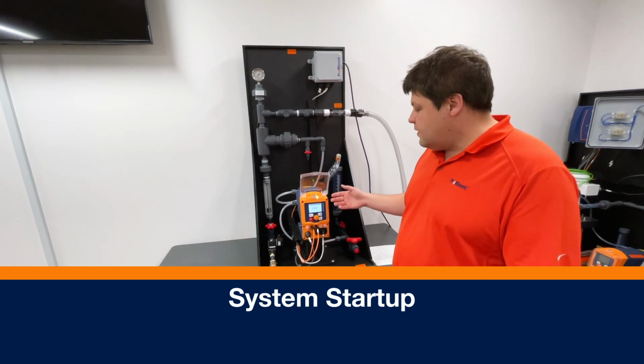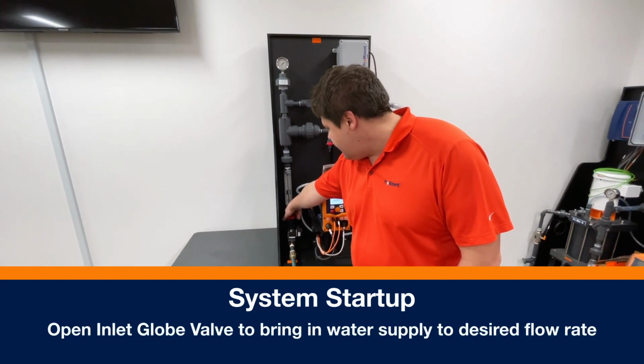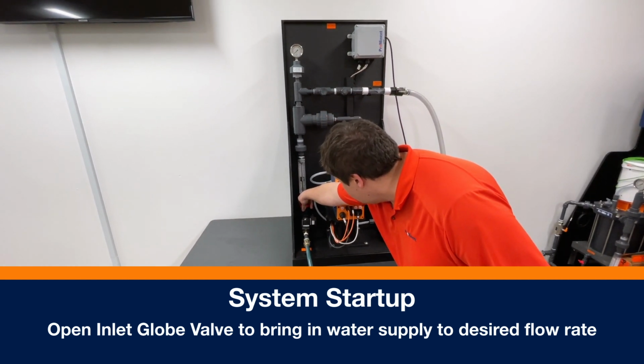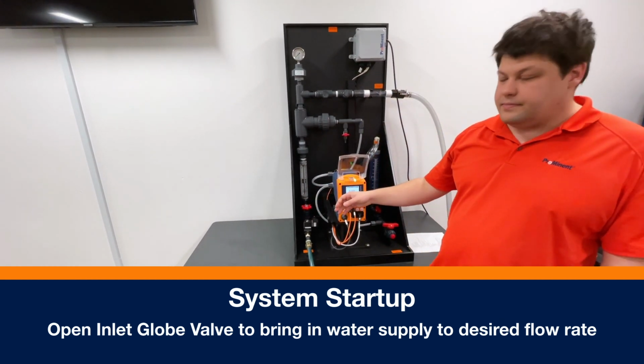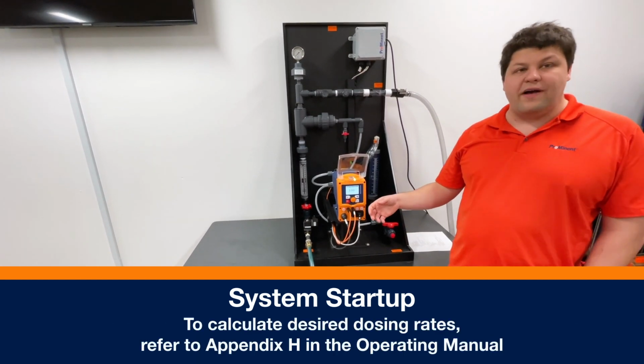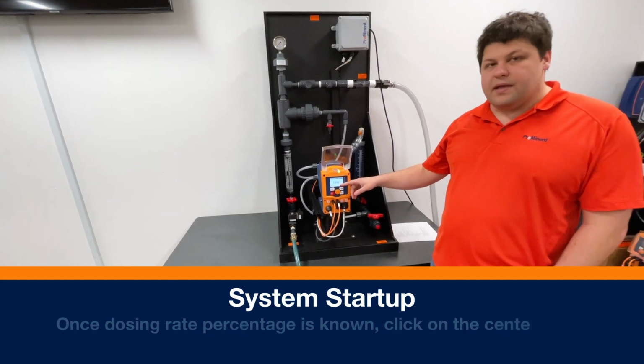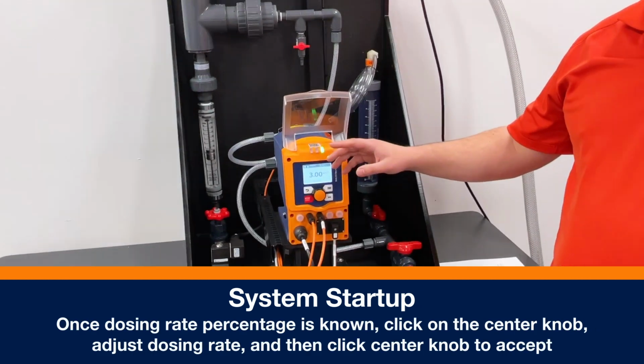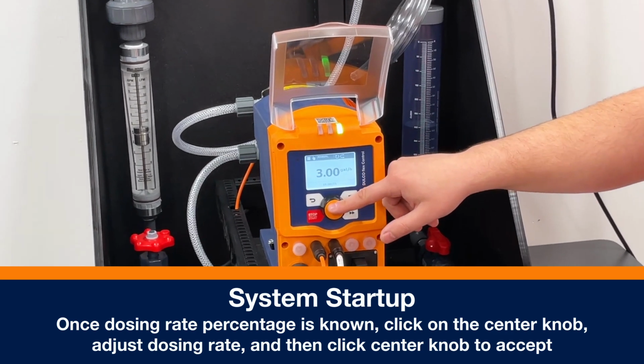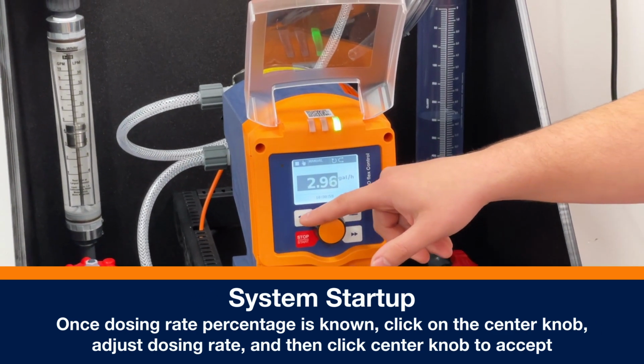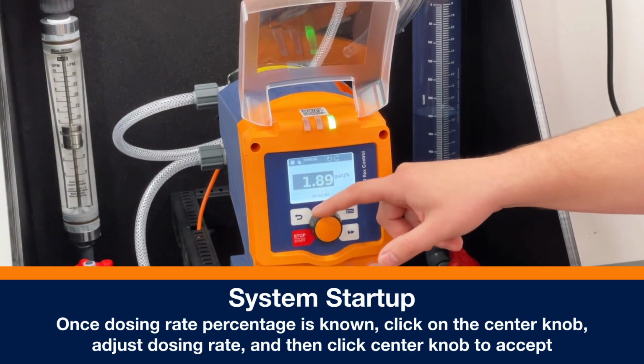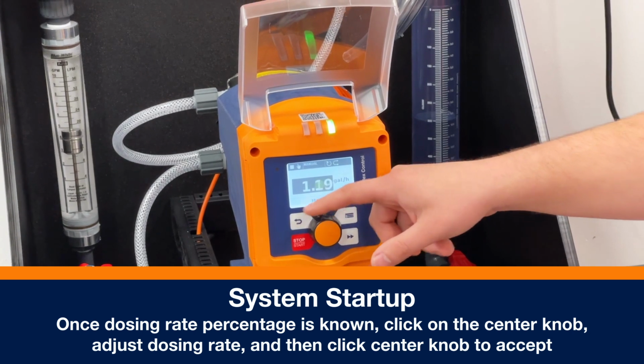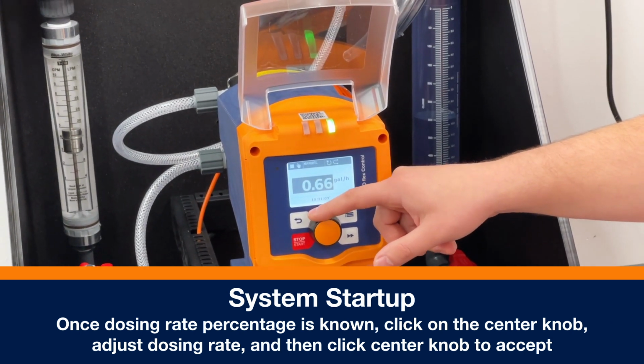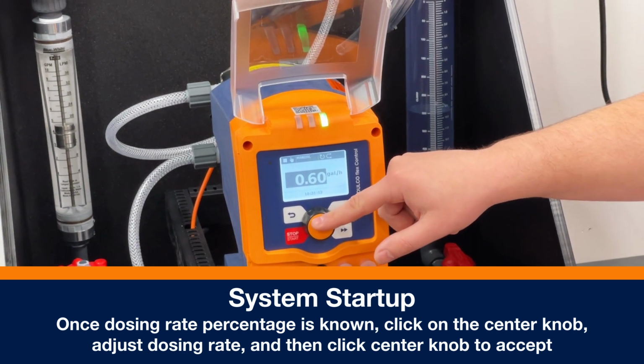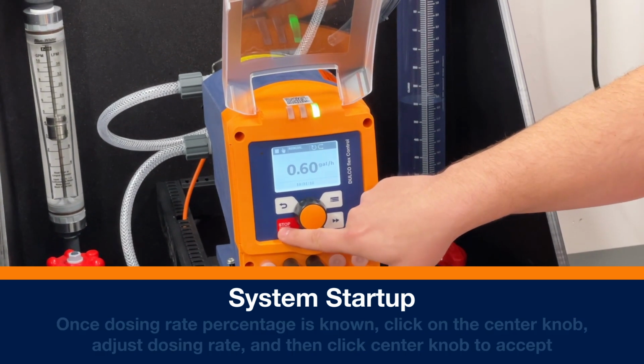We're going to show startup of the unit for the ProMix H system. First, we're going to bring in our water and get it to our desired flow rate. Right here, we're getting about 4 gallons per minute, and we're going to try to make down to a 0.25% solution. Next, we're going to come down to the pump at a 0.25 solution of polymer for the outlet. We want to bring this down to a 0.6 gallon per hour. So we're going to bring our pump down from that 3 gallon per hour where we started down to 0.6. Press the click wheel to enter that, and then we're going to start our pump.